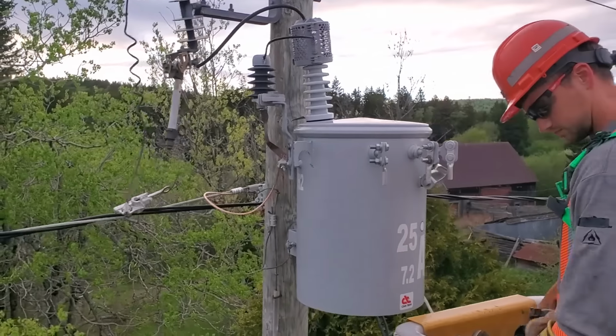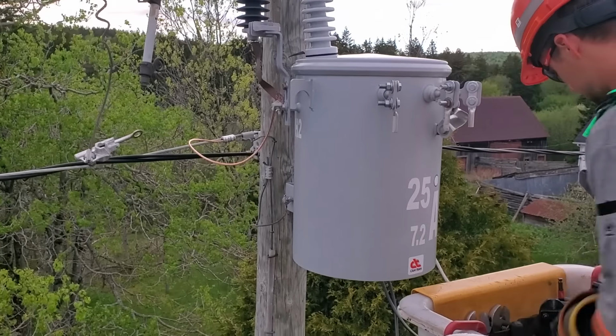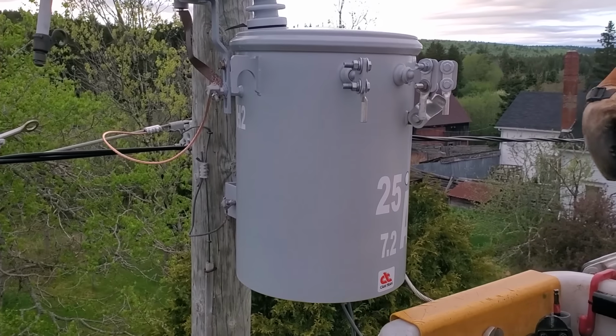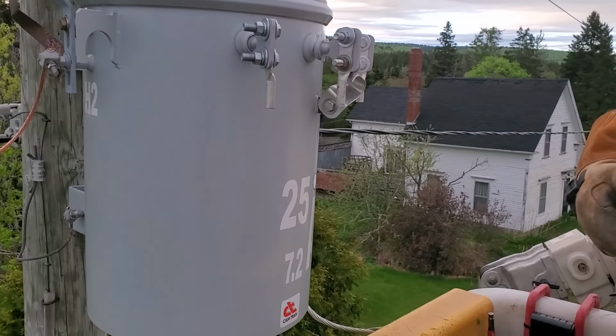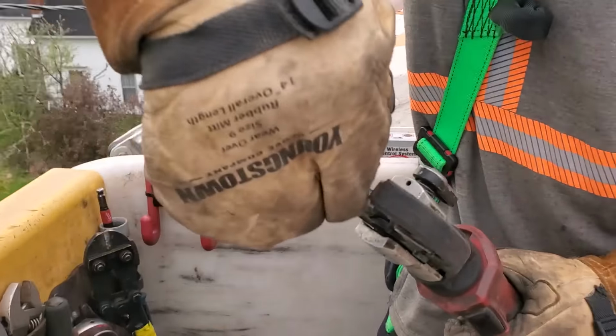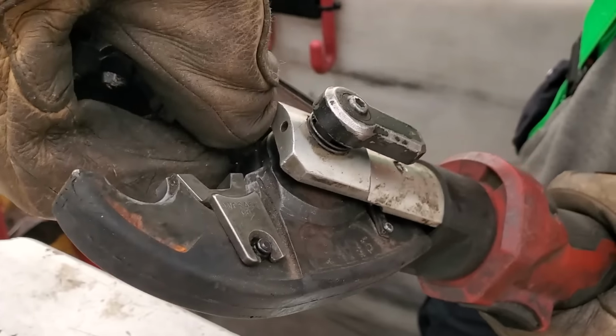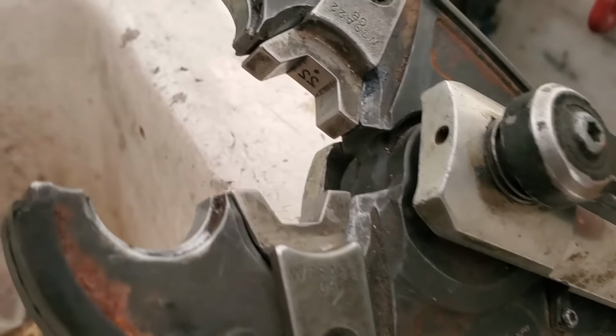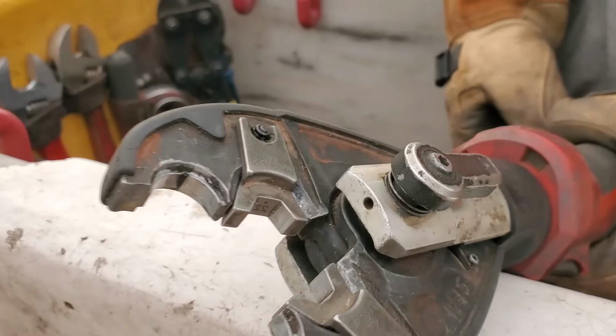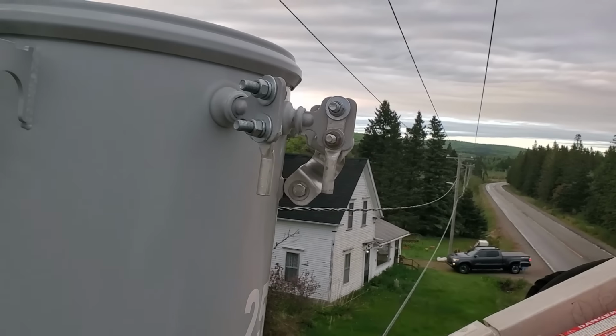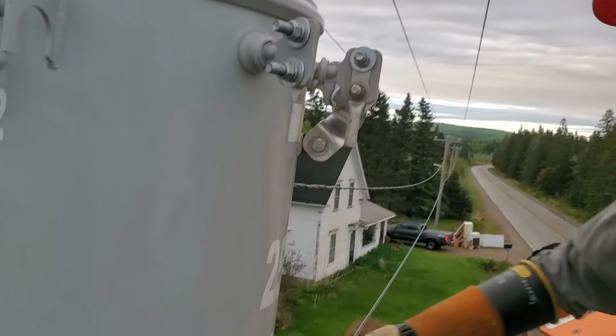He's going to start on the secondary leads. You actually just put the high lugs on and the lead should reach directly into that. It does require some dies. What do we got here? We've got our 5/8 dies, CSA 22 dies, which will fit that 1/0 aluminum.